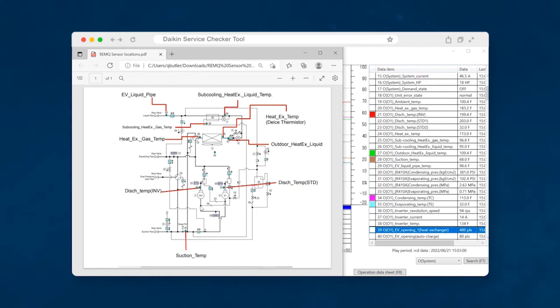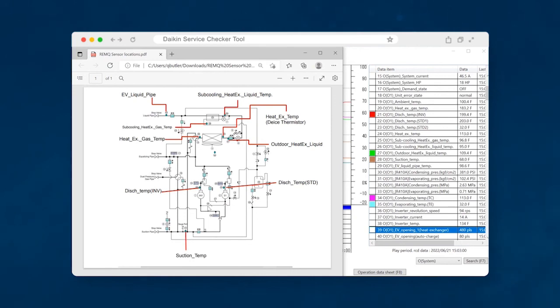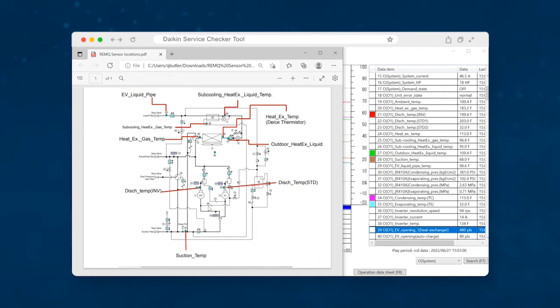But suction pipe temperature, we're measuring it before it goes into the compressor. One thing that you have to watch for on some of the latest vintages of equipment is there's a suction pipe temperature value. And then there's also a compressor suction pipe temperature value. So one thing that you have to keep in mind is where is the oil being injected? Is it injected somewhere between the compressor suction pipe temperature and the field suction pipe temperature value? Because if so, this value is going to be really high. A lot of people automatically assume low charge because they're looking at that compressor suction pipe temperature value. But really all that's there for is to help you determine adequate oil flow.